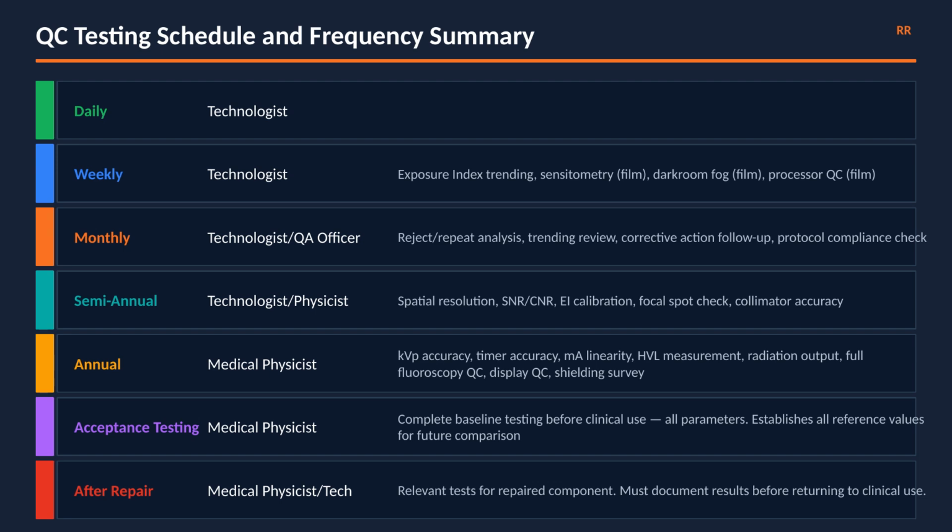Semi-annual, technologist and physicist collaboration: spatial resolution, SNR and CNR, exposure index calibration, focal spot check, and collimator accuracy.